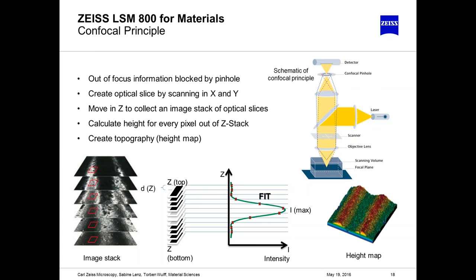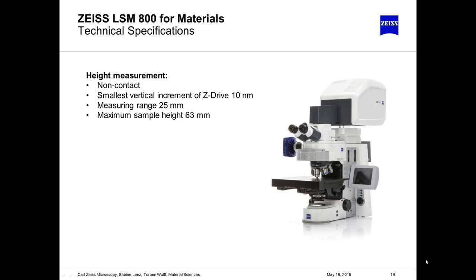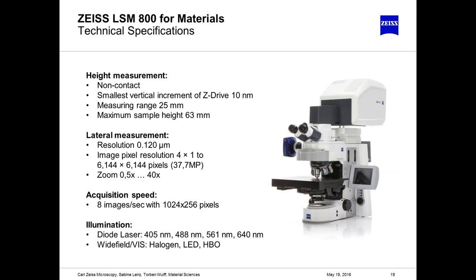Here are some technical data from the LSM 800 for materials. You can position samples with a height up to 63 millimeters under the microscope, and you have a vertical scanning range in the Z direction of up to 25 millimeters. Thanks to the high performance optics, we achieve lateral resolutions down to 120 nanometers with an amazing pixel count of 37.7 megapixels. For different applications, especially for fluorescence with synthetic materials, a large variety of illumination possibilities are offered.